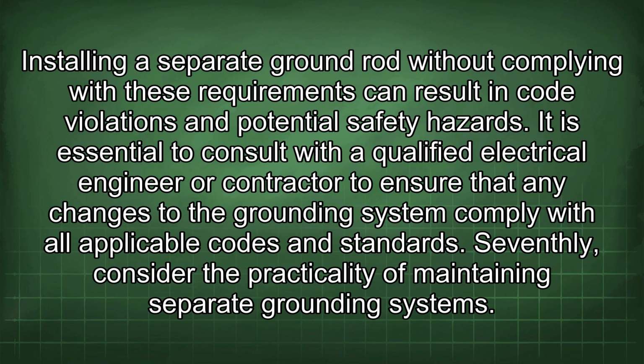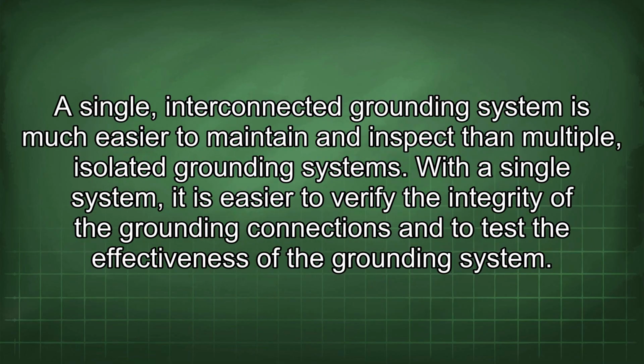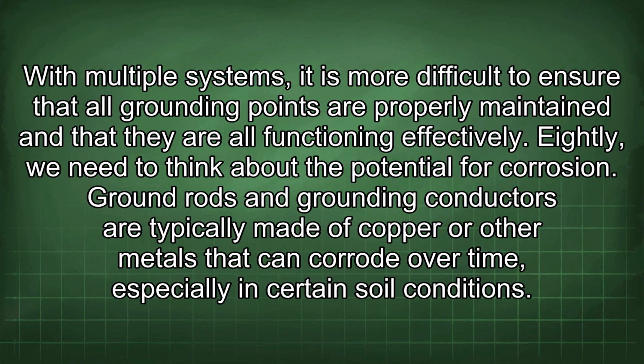Seventhly, consider the practicality of maintaining separate grounding systems. A single, interconnected grounding system is much easier to maintain and inspect than multiple, isolated grounding systems. With this single system, it is easier to verify the integrity of the grounding connections and to test the effectiveness of the grounding system. With multiple systems, it is more difficult to ensure that all grounding points are properly maintained and that they are all functioning effectively.